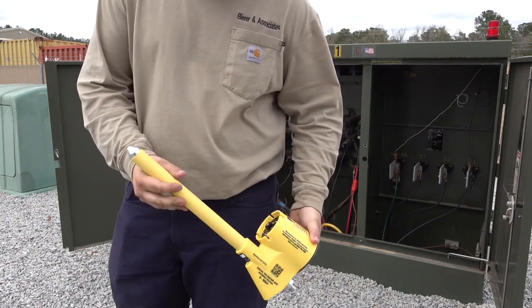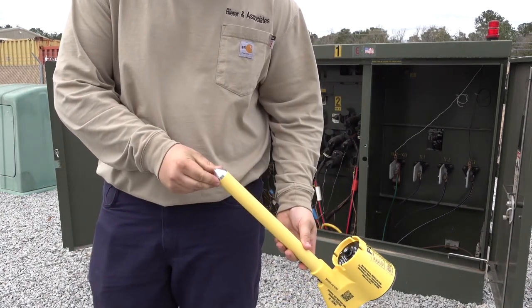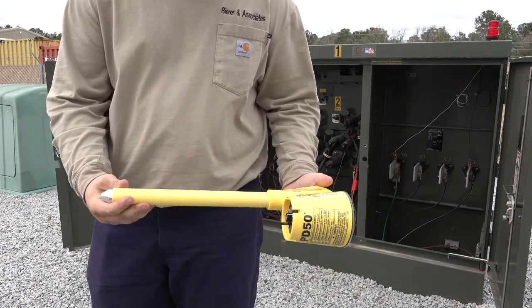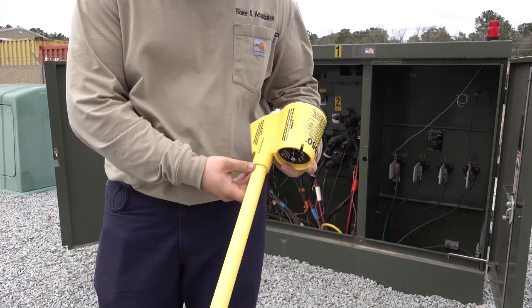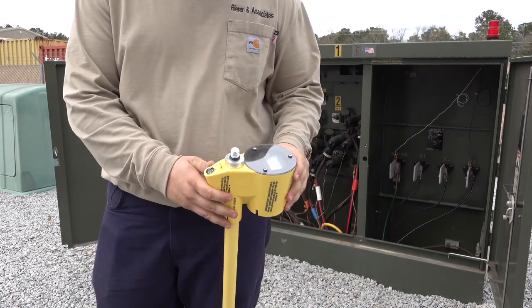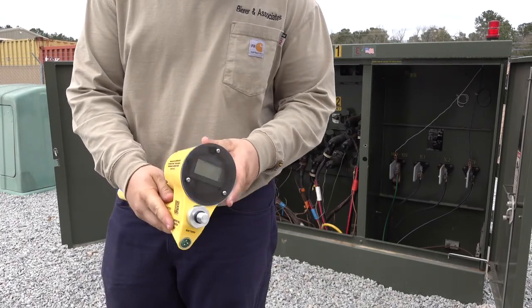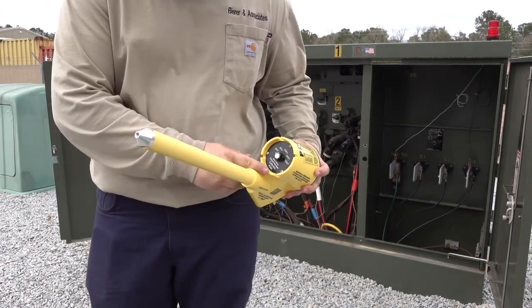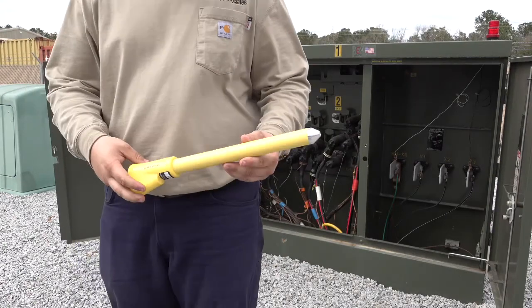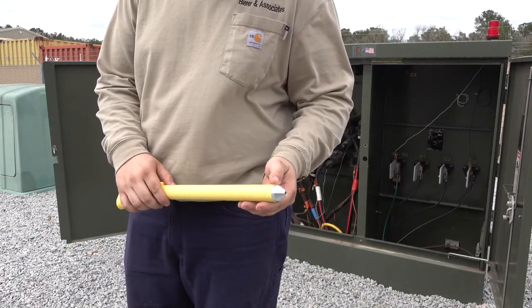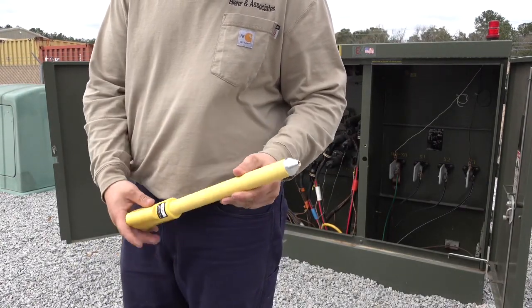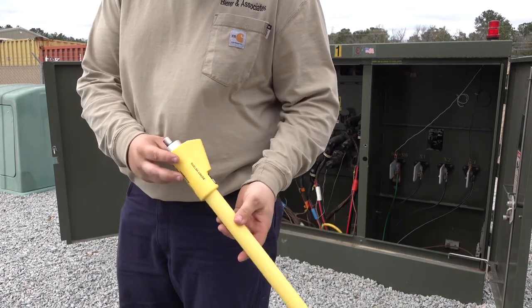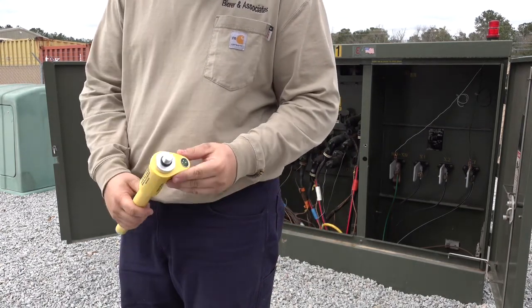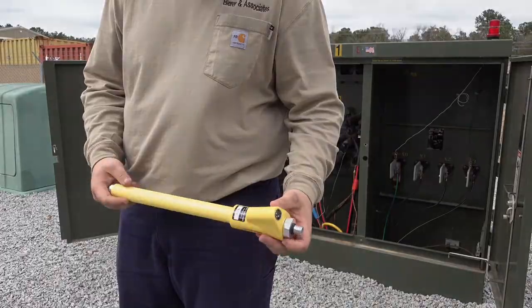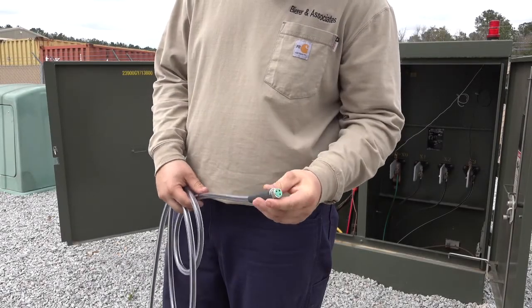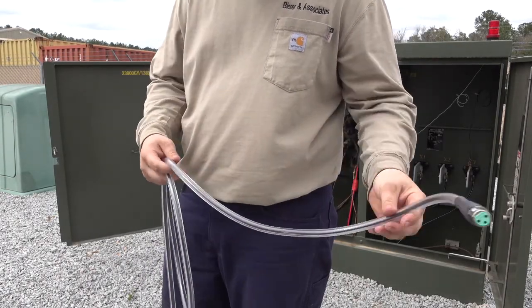Before we begin phasing capacitive test points using the Bierer PD50 all-purpose utility meter, we want to take a few minutes and do a visual inspection of all the tool components. Make sure the meter probe is free from any dirt, grease, cracks, or any deep scratches that may impair the built-in safety features of the tool. Also take a few moments to inspect the second probe and the interconnect cable in the same manner as the meter probe.